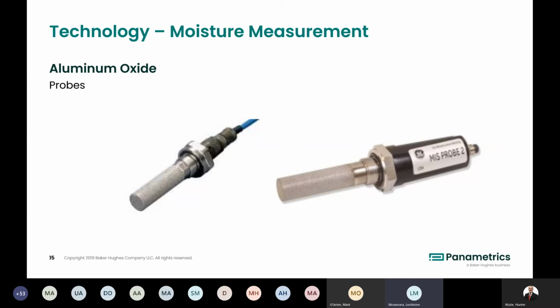just start running at the probe and going, hey, there's something wrong with the probe. Look at your sample system, look at your process conditions, step back and look at the big picture, because the measurement is from the sample point to the sensor and possibly beyond. But yeah, in terms of kind of hard failures, open circuit and short circuit are the two main ones. Okay. We find as well that a lot of the issues, the probe will highlight if there's an issue, but the issue mightn't necessarily be with the probe. So you could have a leak in your sample system. The customer might have a filter that's blocked upstream. These kinds of things will ultimately show up in the moisture sensor itself. It gives you a reading. So then it's how you interpret that reading. It's really about education sometimes.